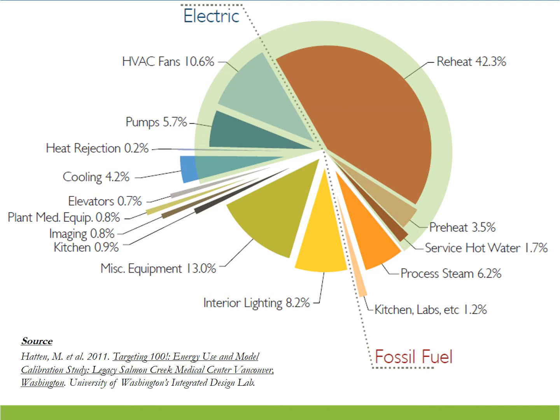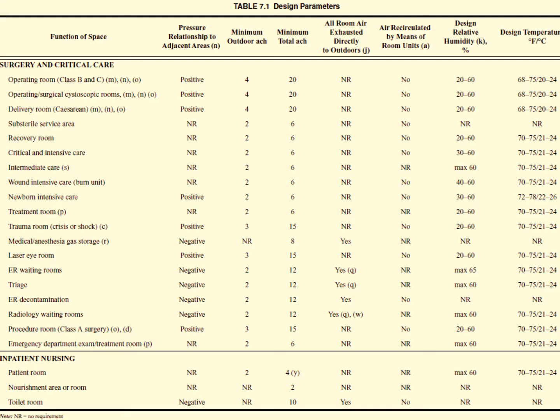Reheat energy comes from a very understandable place. Reheat energy comes from this table. In hospitals, we use this table, and it's got air change rates and room pressures. When I was in college studying to be a mechanical engineer, I took an HVAC class. I still have that textbook in my garage, and it has a version of this table in it. So from day one, I learned this is how you do hospital air change rates and room pressures. This table has existed largely in the same form since about 1968.